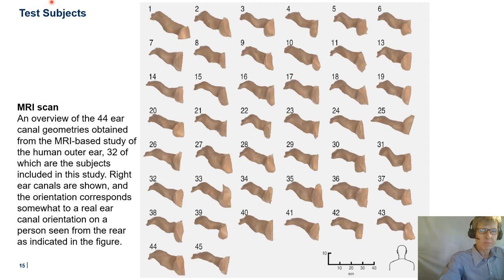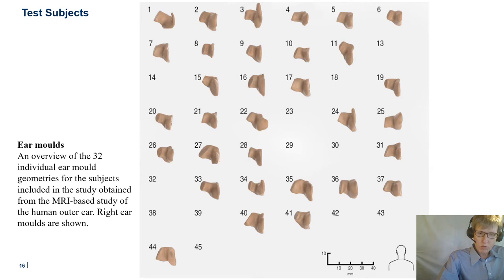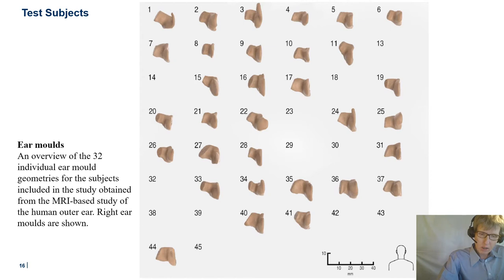From the geometry data, individual ear molds for all subjects were fabricated. This ensured that an optimal seal and fit was obtained when inserting the impedance probe assembly into the ear canal, and that the measurement position at the measurement plane relative to the eardrum was known. The measurement plane of the ear mold is positioned somewhere between the first and second bend in the ear canal. An attempt was made to have approximately the same insertion depth across subjects, which was difficult due to large variation in ear canal geometries and the need to keep the session comfortable for the subject.